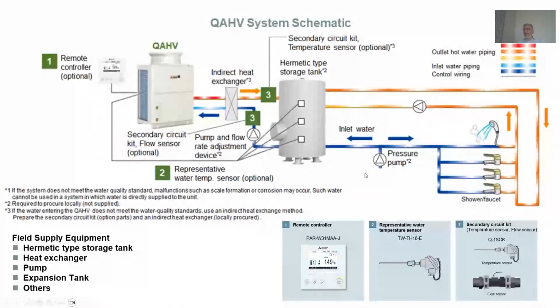In a typical application, water comes into your facility and goes to the bottom of the tank, from where the pump circulates it on a secondary side. It does a heat exchange with the hot water produced by the CO2 heat pump, and you get hot water which is stored in the tank and used for domestic use. You mix it at the faucet to get the required temperature.